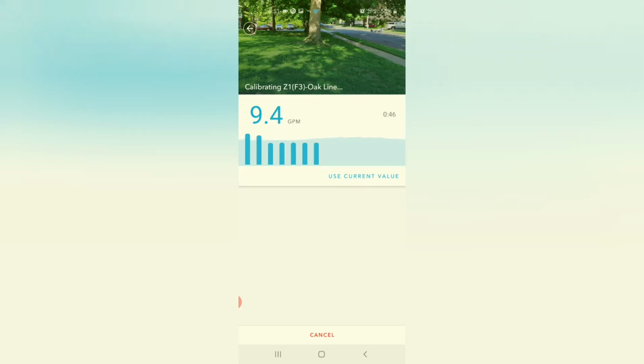You can set up a longer calibration. I wouldn't do it shorter, because at the very beginning the flow reading, like 13.3, is unusual — that's just at startup. I want the sprinklers running normally, once trapped air is taken out, so it finds its own golden spot.